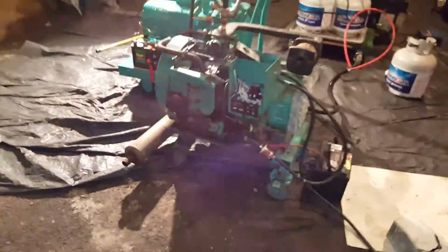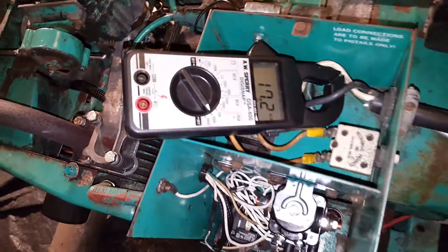Let's see what happens if I shut this valve off. Going down to 24 amps. Now let's shut this valve off over here — that's off. Just hear a little bit of motor variation. Down to 17 amps.